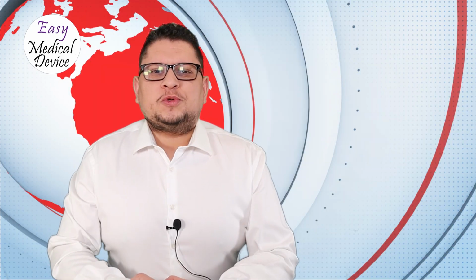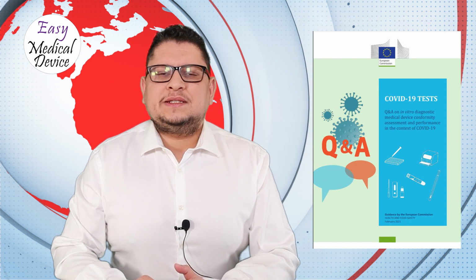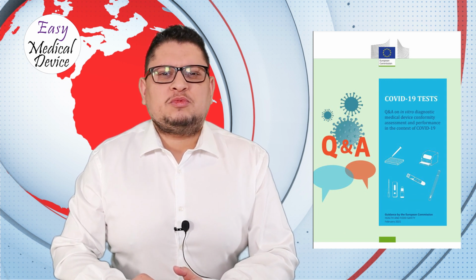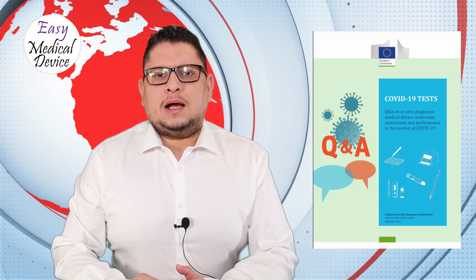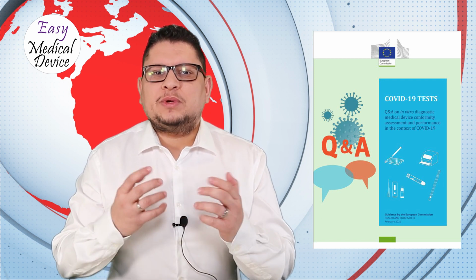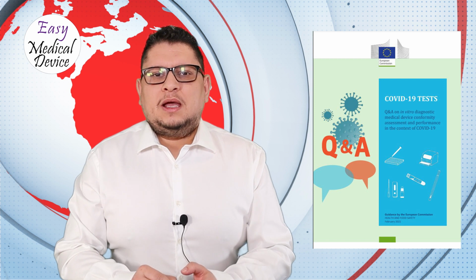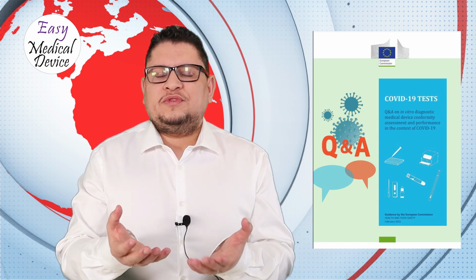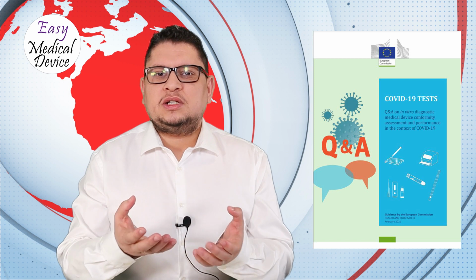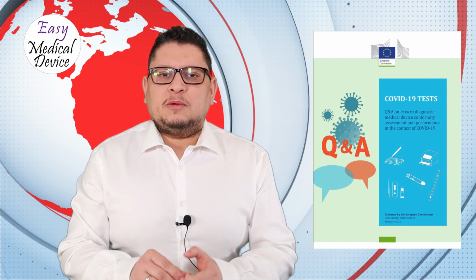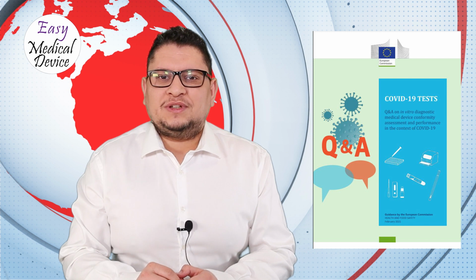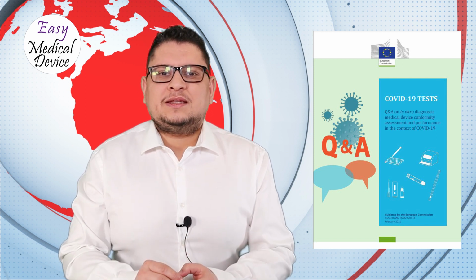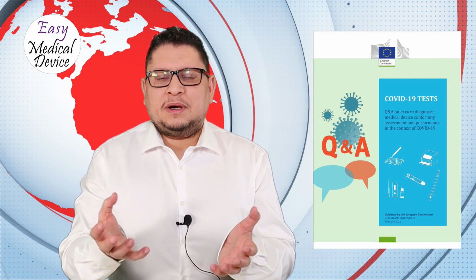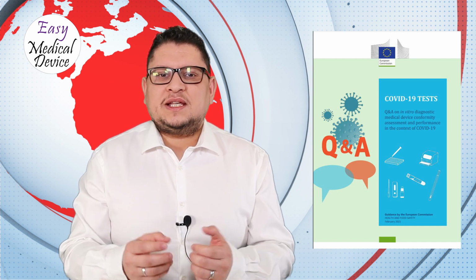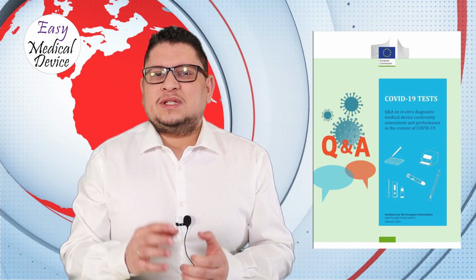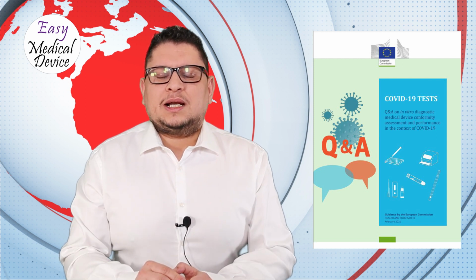Okay, the European Commission also issued a document related to COVID-19 tests, a question and answer. It provides a lot of information about what those tests are, how they are regulated, how you can place them on the market. For example, you have to understand that if a COVID-19 test is made to be used by a professional person, then there is no need of a notified body. But as soon as you say that this COVID-19 test can be used by a layperson, by anybody by itself, so self-testing, then a notified body should be involved. So these are the kind of elements that are clarified in this document.